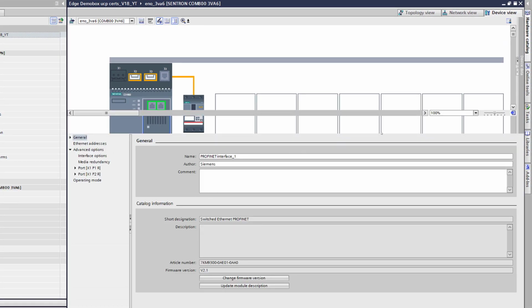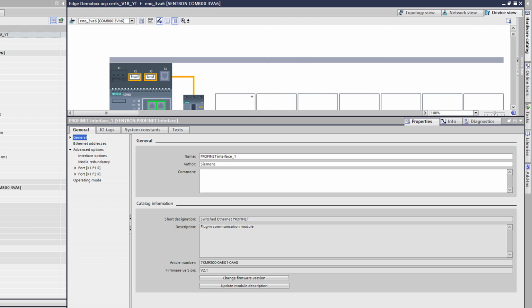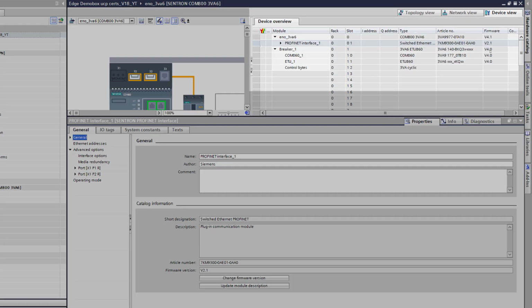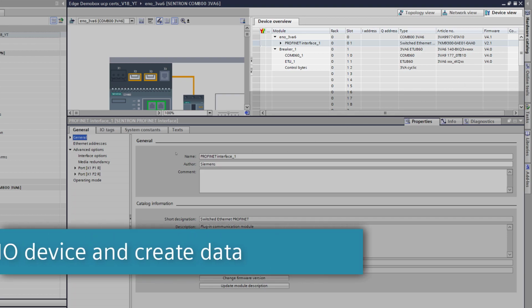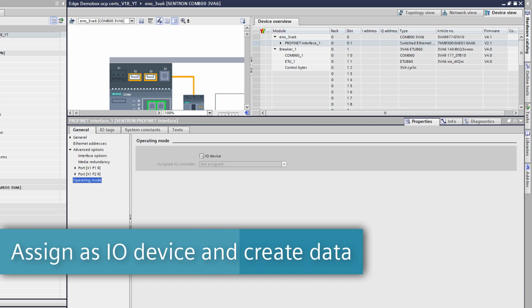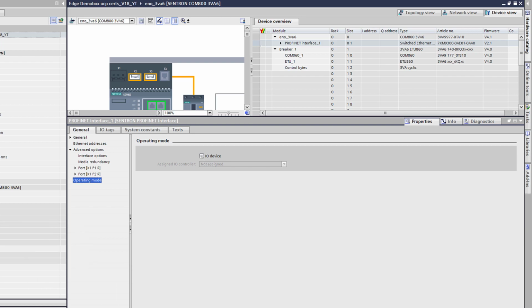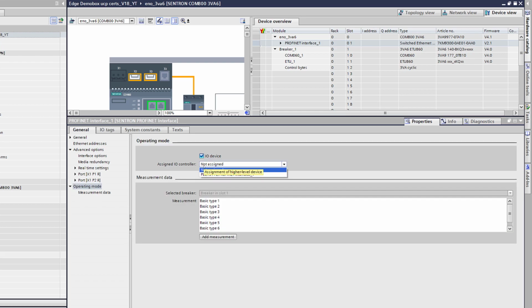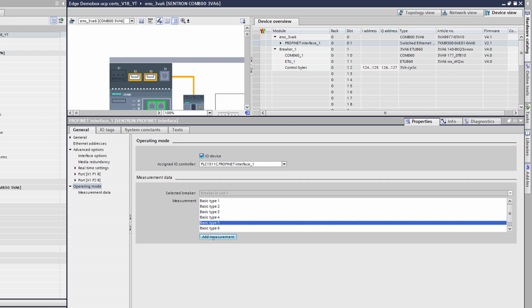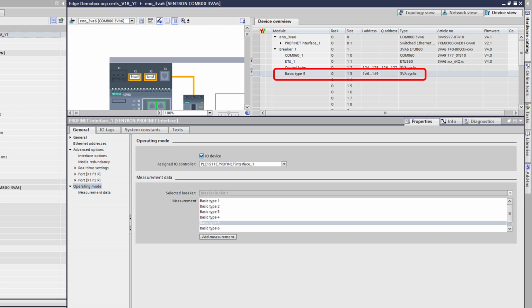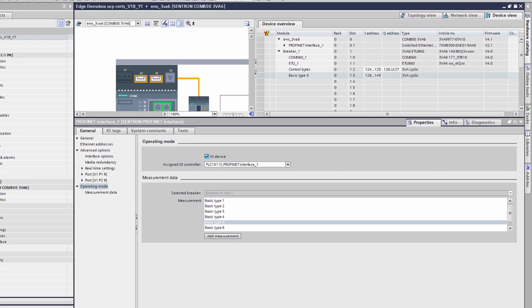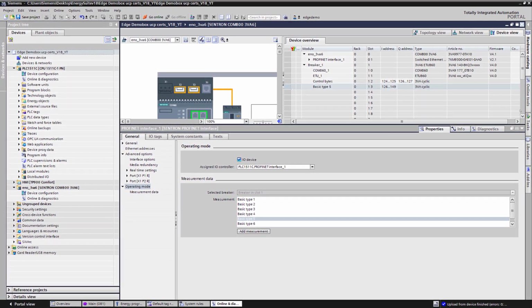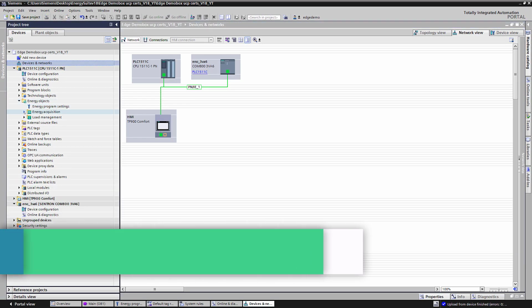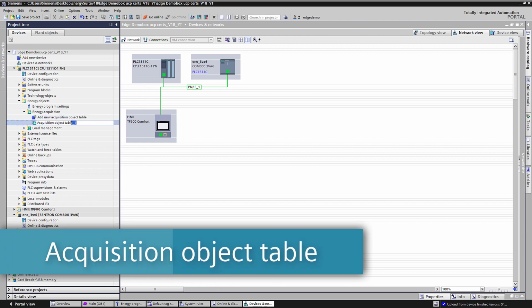As I just mentioned, within the device view, it's pretty easy to adjust the parameters within the properties area of the device, as well as seeing things like the firmware of the relevant pieces underneath the device overview. Next, it's time to assign the I/O device and create energy data. Checking the I/O device box and then selecting PLC 1511C allows us to assign the I/O device to the I/O controller. Notice the insertion of the control bytes, as well as if we insert measurement data, you will find the data there also. Under the Energy Objects folder, you'll see the ability to add a new acquisition object table.